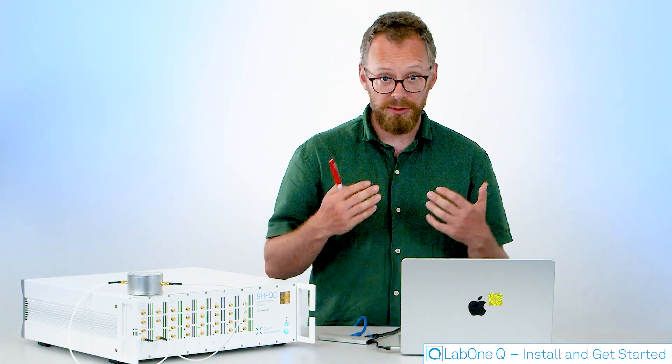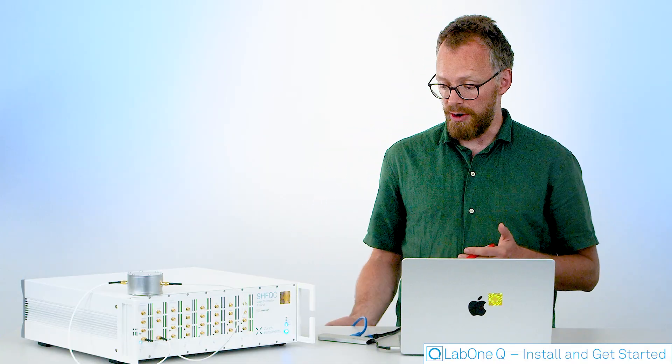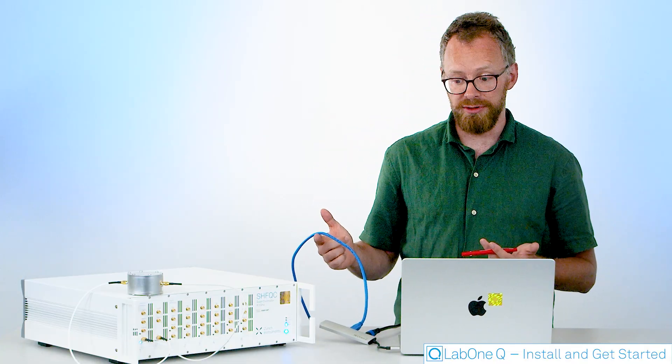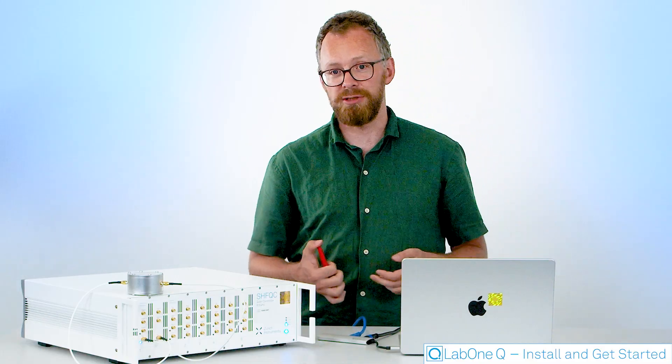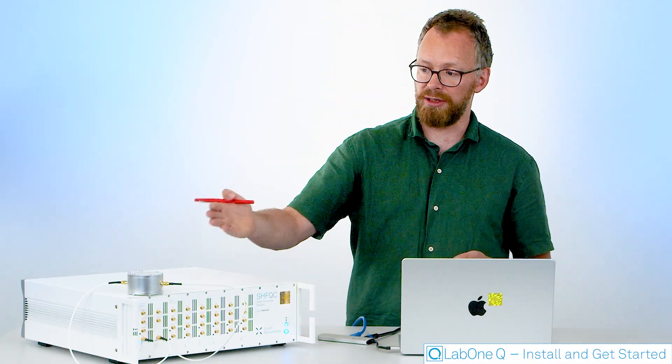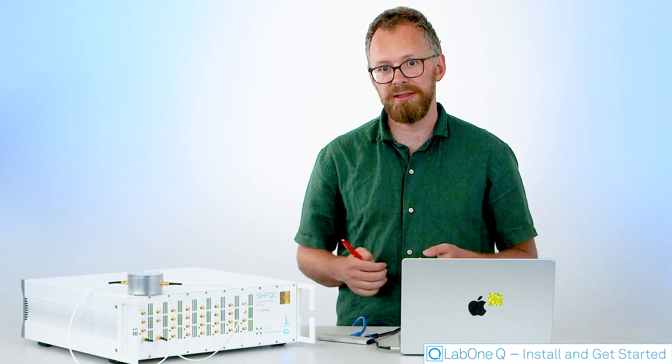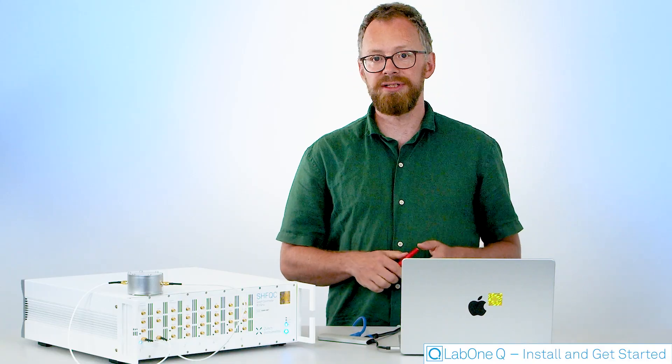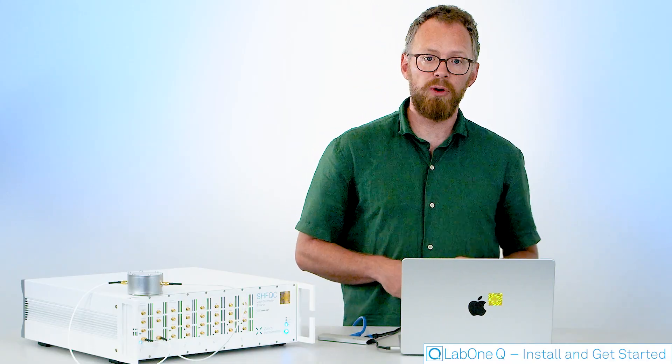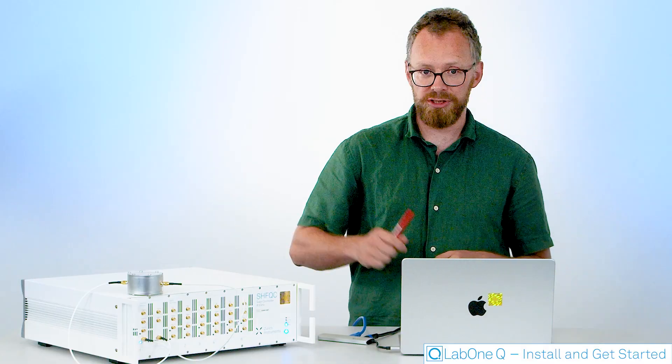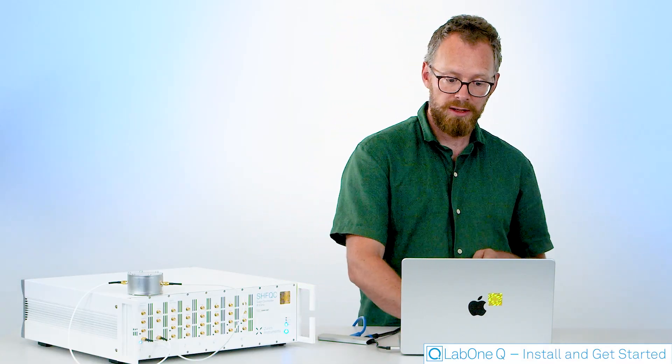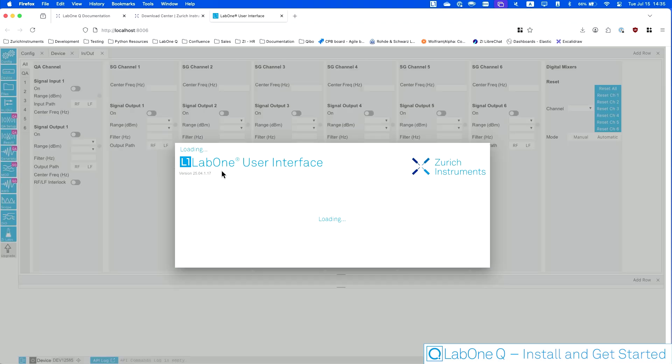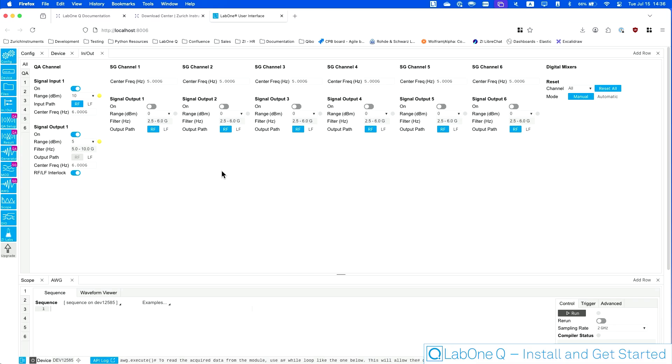There's different ways of how you can connect to the instrument. For example, how I did it here is directly via USB connected to my computer. In most situations probably Ethernet will be the better choice so you can connect the instrument to your local Ethernet within your lab. As long as you're in the same Ethernet with your computer, LabOne will find the instrument within the network and allow you to connect to it. When I connect to it within this interface, I will now see a graphical user interface that gives me an overview of all the parameters and properties of this instrument.